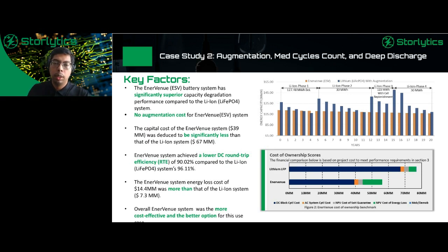Compared to that, in this particular case, we were doing 3 augmentation cycles. So we started with 127.5 megawatt hour, around 25% overbuilt for lithium. Around year 5, we needed to add more capacity to maintain more than 100 megawatt hour. So we did around 30 megawatt hour of augmentation at phase 2.